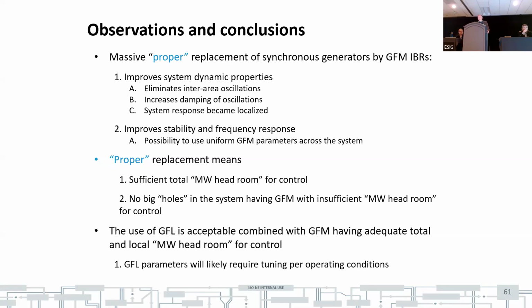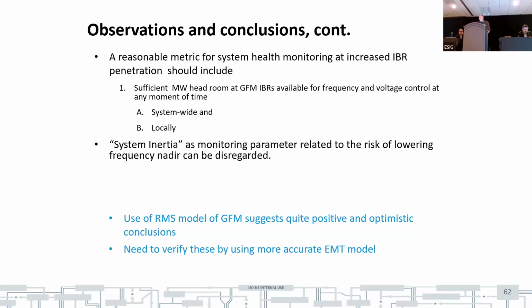So, what does it mean, right or proper replacement? That means practically two things. You need to have sufficient total megawatt headroom for control, and it should be uniformly allocated across the system. So regarding grid following inverters, yes, they could be in the system, but with proper combination with grid forming inverters. And the reasonable metric based on this research is basically only one parameter. You need to make sure that you have a sufficient amount of total megawatt headroom for grid forming inverters in the system. And that should be system-wide and local.